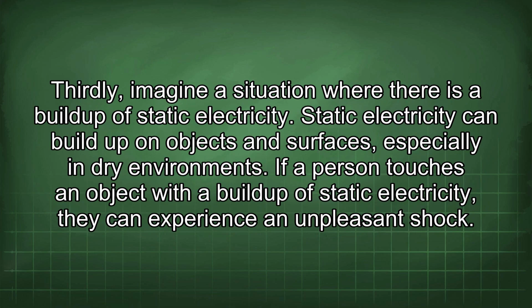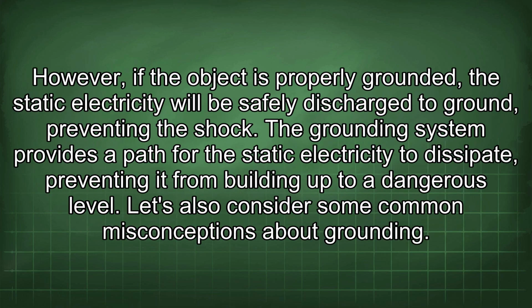Thirdly, imagine a situation where there is a buildup of static electricity. Static electricity can build up on objects and surfaces, especially in dry environments. If a person touches an object with a buildup of static electricity, they can experience an unpleasant shock. However, if the object is properly grounded, the static electricity will be safely discharged to ground, preventing the shock. The grounding system provides a path for the static electricity to dissipate, preventing it from building up to a dangerous level.